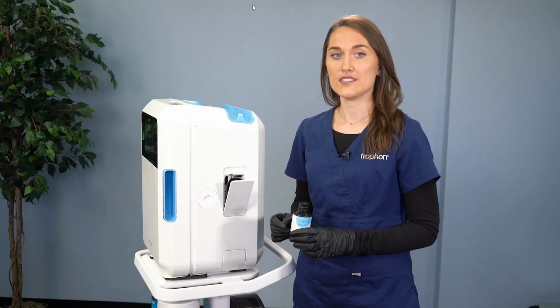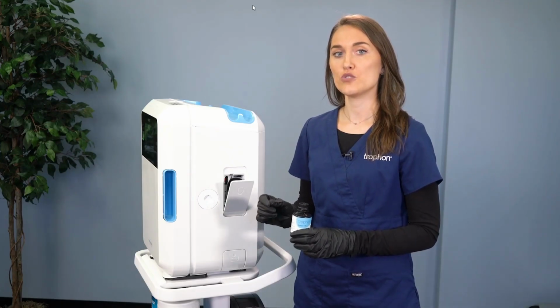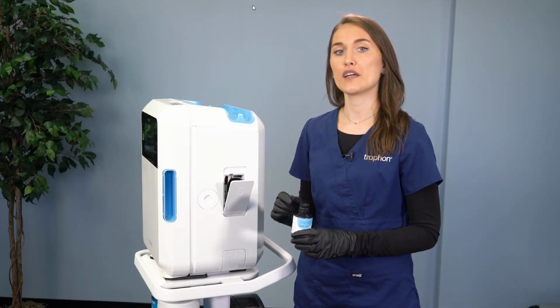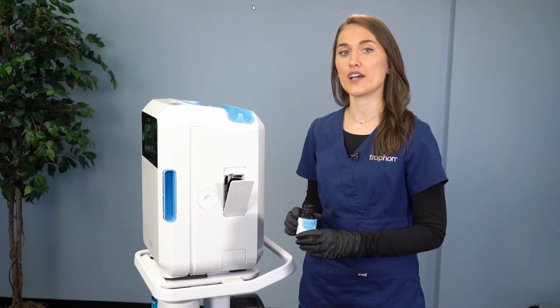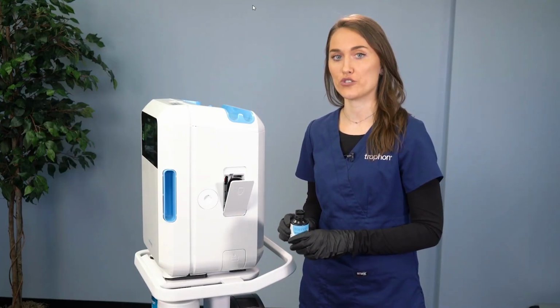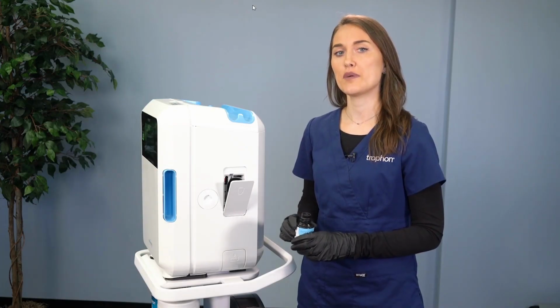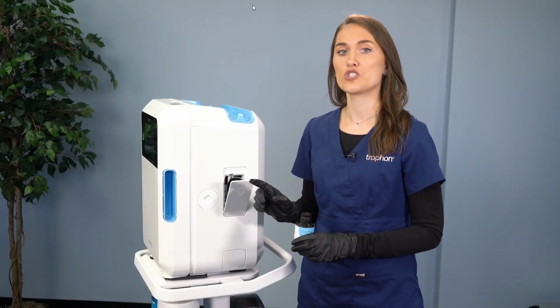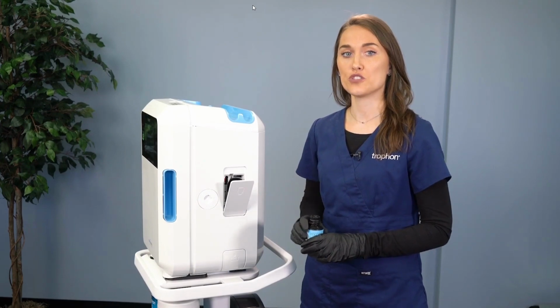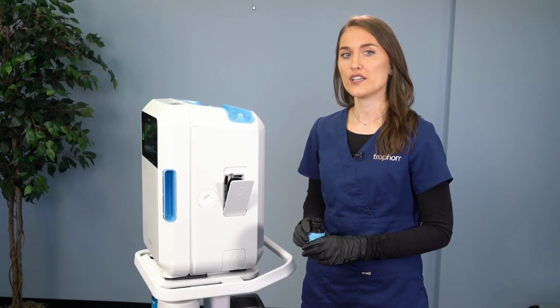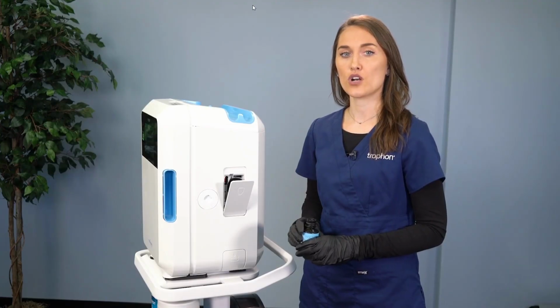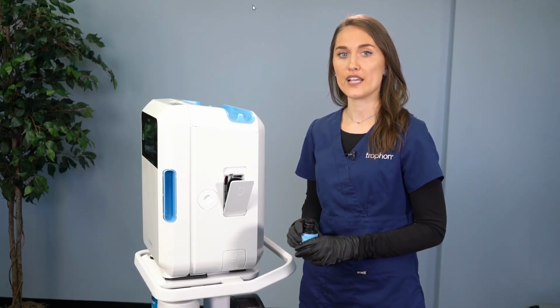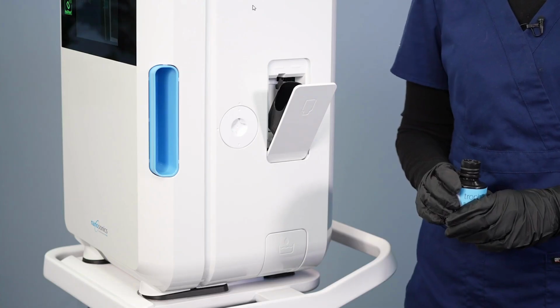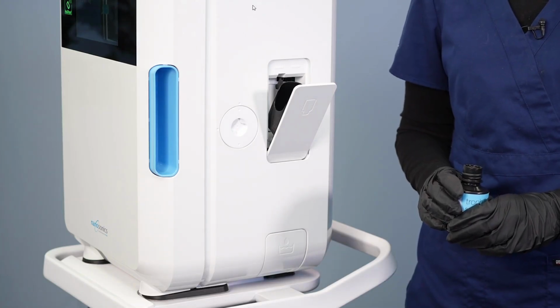On the other hand, if the cartridge expires, users will be required to remove the expired disinfectant from the inside of the device before inserting another cartridge. This can be achieved by running a purge cycle, which the display will instruct the user to do. When the purge cycle is initiated, the device will start removing the disinfectant by breaking it down to its byproducts, which are oxygen and water.